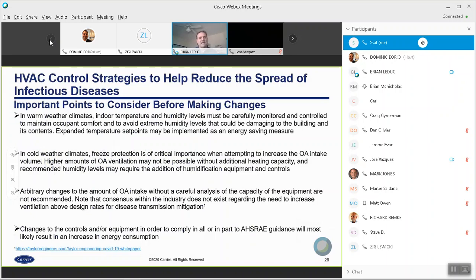Again, for probably the 8th time, expanding set points could be beneficial as an energy savings measure, because increasing ventilation in and of itself is probably going to use more energy. So ideally, you want to try to help offset that as much as you can. In cold weather climates, freeze protection is obviously an issue. A lot of this guidance doesn't seem to address what's going to happen in the winter if we're still worried about COVID-19. Freeze protection is key.